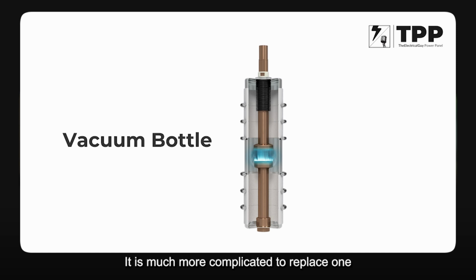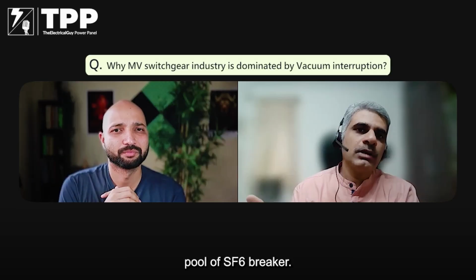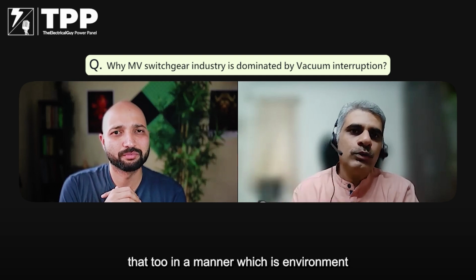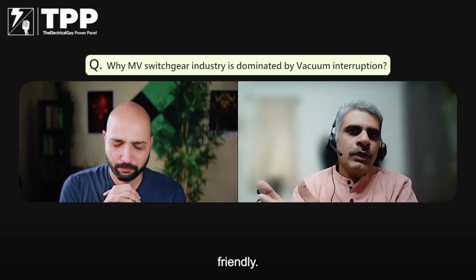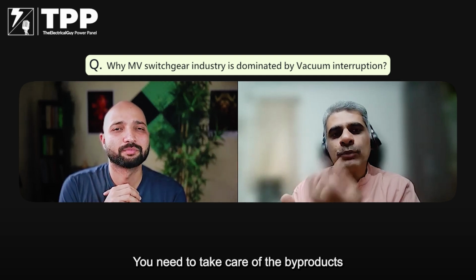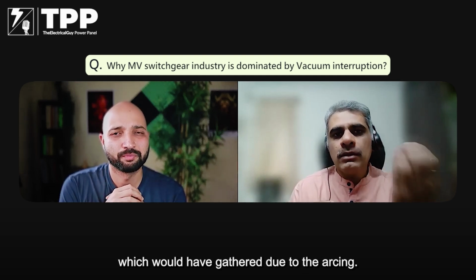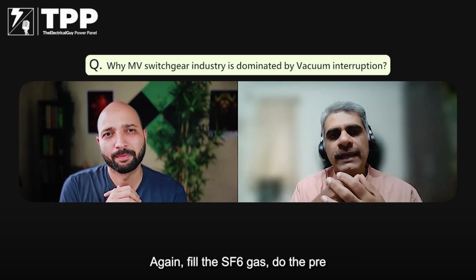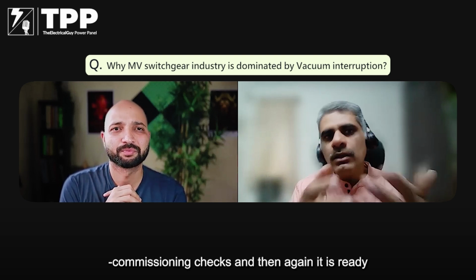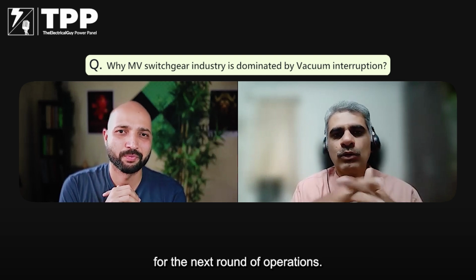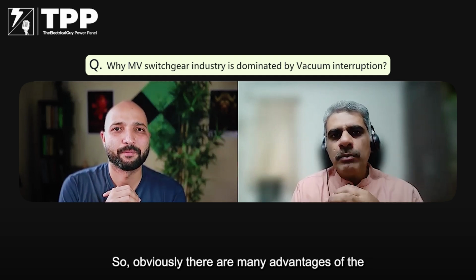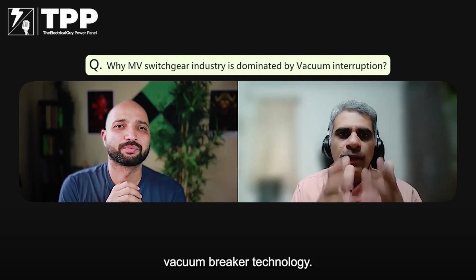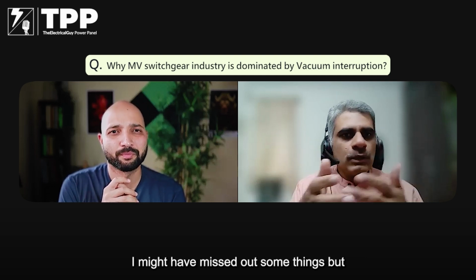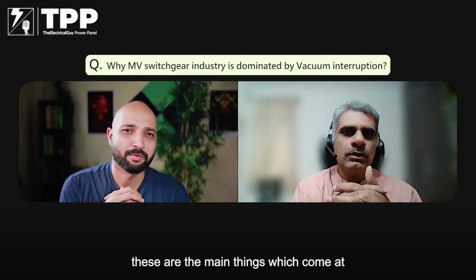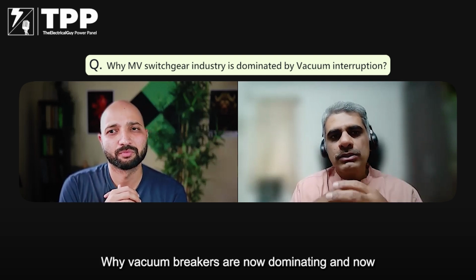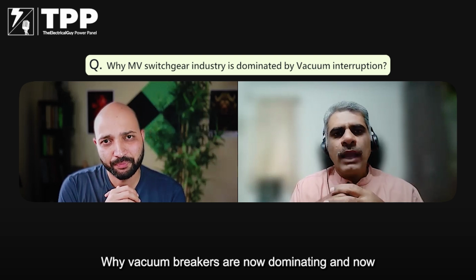It's much more complicated to replace one pole of an SF6 breaker. You need to drain out the gas, and that too in a manner which is environment friendly. You need to take care of the byproducts which would have gathered due to the arcing. Again, fill the SF6 gas, do the pre-commissioning checks, and then again it's ready for the next round of operations. So obviously there are many advantages of the vacuum breaker technology. I might have missed out some things, but these are the main things which come at the top of my mind. Why vacuum breakers are now dominating, and now it's a complete dominance.